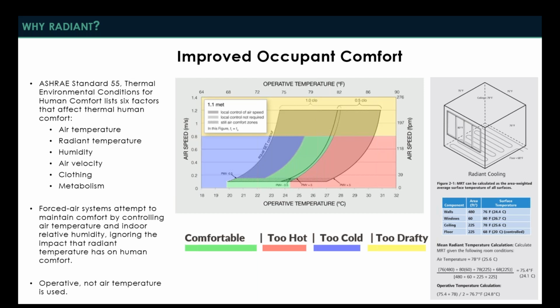Now, the image in the center is really showing the sweet spot for operative temperature and airspeed in a space. The point to make here is that operative temperature is not the same thing as air temperature. And that's very important in radiant systems because operative temperature is essentially the combination of what is known as mean radiant temperature and air temperature. I won't get into too much of the science behind the image on the right, but I included it just to make the point that when you do the calculation and take into account the various surface temperatures in a room and the air temperatures within a space, you can find that a space that has an air temperature of 78 degrees actually has an operative temperature of closer to 76.7. What that means is that someone can be comfortable in a space where the thermostat has been pushed up to 78 degrees. And anytime we can raise the thermostat temperature, that's going to improve the efficiency of our buildings.